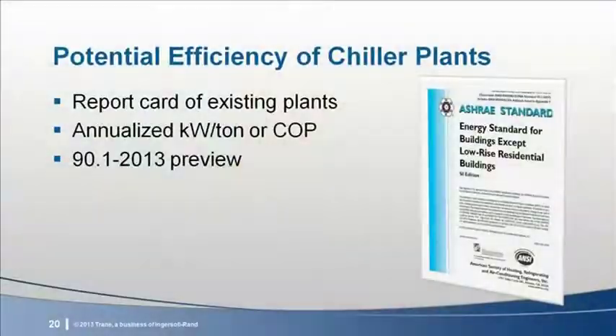Now, one of the things we're going to be exploring today is the potential efficiency of chiller plants so that we can figure out how best to operate them. Now, as you look at your existing plants, what kinds of performance should you be looking for? One metric that seems to fall out of the discussion on chiller plant efficiency is kW per ton. Now, I'm not talking about an instantaneous metric, but an annualized metric, kWh per ton hours. And what are the relevant changes in 90.1/2013 that we can use to define what a minimally compliant chiller plant looks and performs like?